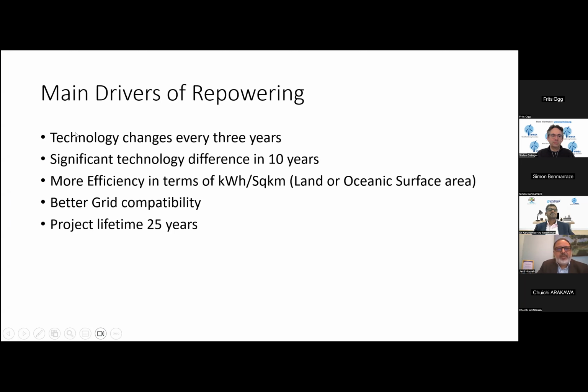We discussed these main drivers of repowering. Technology changes every 3 years, and there is a very significant technology difference that happens over around 10 years. In 2014, we were setting up 2 megawatt, or 2.1 megawatt, wind turbines, but at 80 meter hub height. Now we do the same rating, 2.1 megawatt, at 140 meter hub height, with a very different rotor diameter. So per megawatt or per kilowatt generation is vastly different from what it was earlier. This has also enabled us to harness sites which we earlier considered not very attractive in terms of wind power.